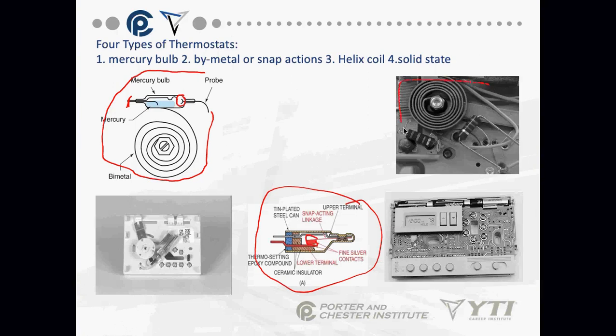Okay, our helix coil is right there. The helix coil, again, is a bimetal coil. Again, all bimetal means is that there are two different types of metals that expand and contract at different rates that are sandwiched together. As it heats up or cools down, it's going to expand or contract and thus change the shape of the coil. Okay, so again, bimetals there.